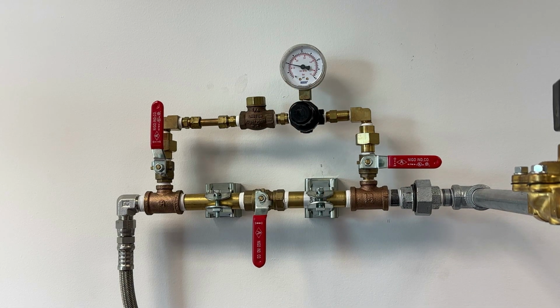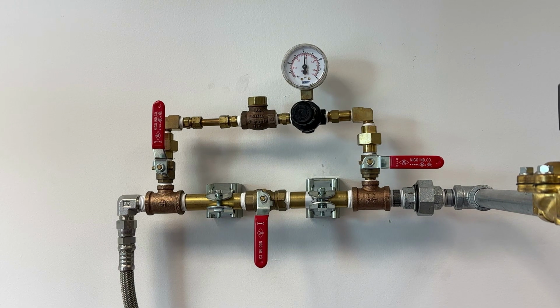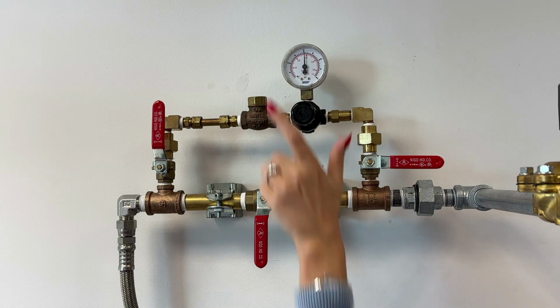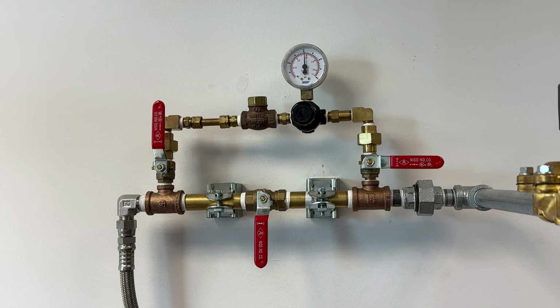Note, always approach the desired pressure from a lower pressure to avoid minor readjustment after making a change in pressure setting. Once the correct sprinkler system pressure has been set, push the adjustment knob in until it clicks into the locked position. You have now field adjusted the pressure setting and can continue the installation process.